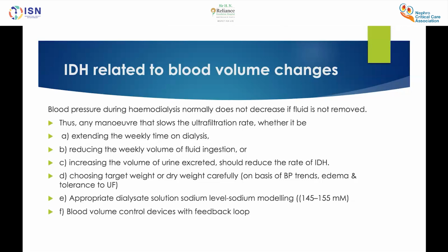Appropriate dialysate solution sodium level, which is also called sodium modeling. It's around 145 to 155. And blood volume control devices with feedback loop.